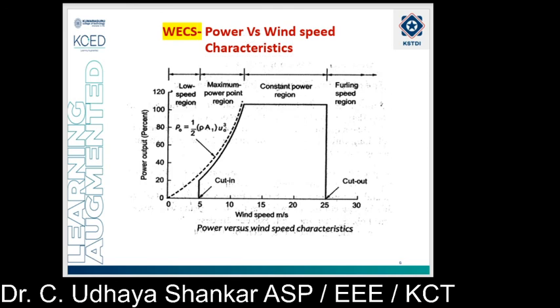In case of wind speed characteristics, there are four different regions. The first is the low speed region — that is the speed between 0 and cut-in speed. In this region, the turbine is kept in the braked position until the minimum wind speed of about 5 meters per second, known as the cut-in speed, becomes available. Below this speed, the operation of the turbine is not efficient — the losses will be very high.